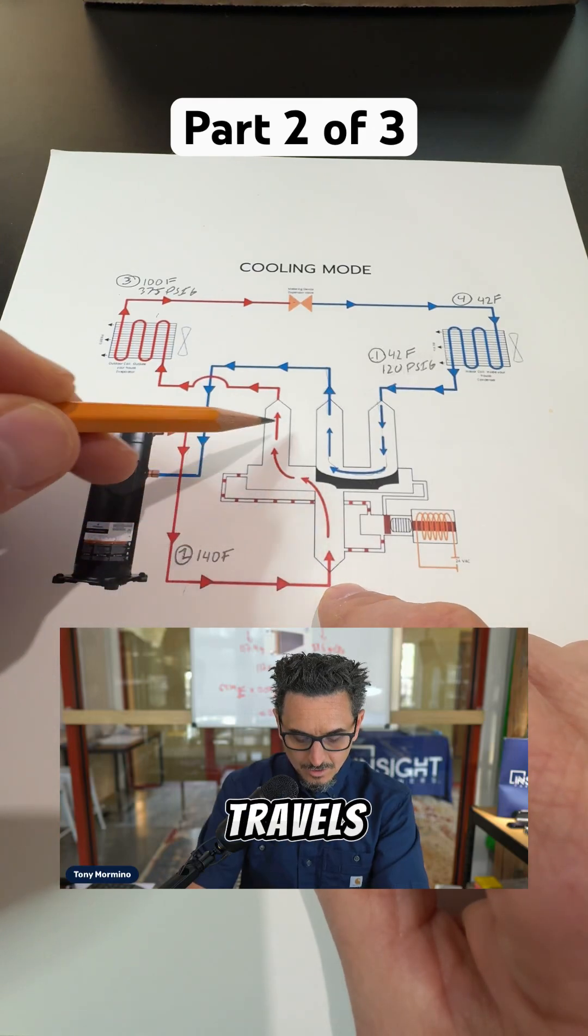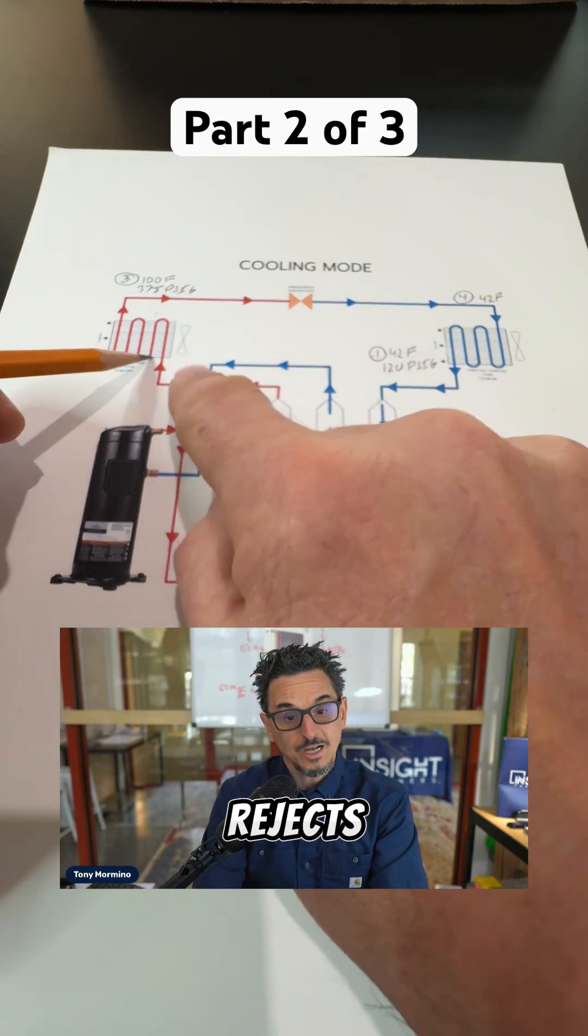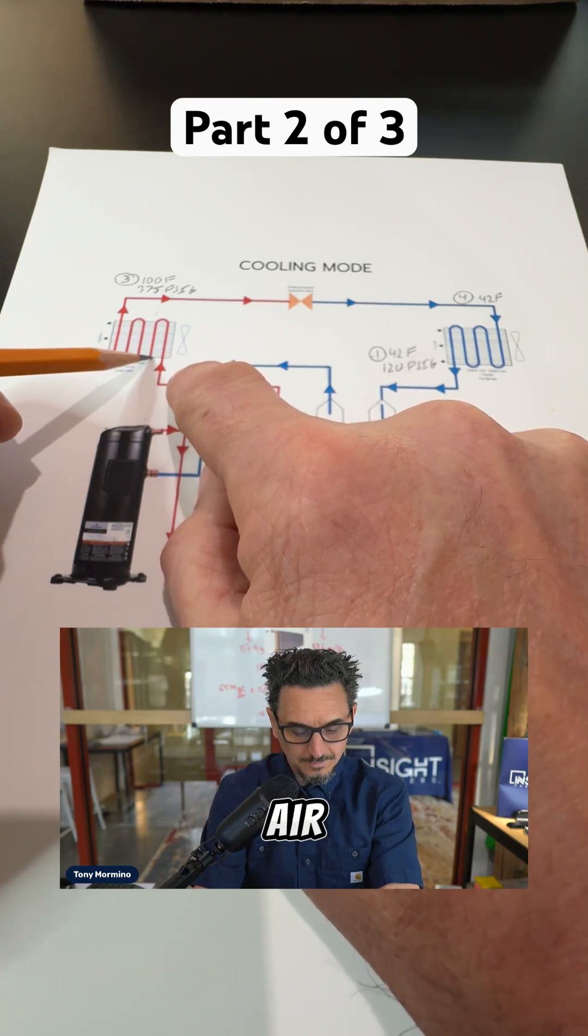Discharge from the compressor travels to the condenser where it rejects the heat of the refrigerant to the relatively cool outdoor air, lowering the temperature to approximately 100 degrees.